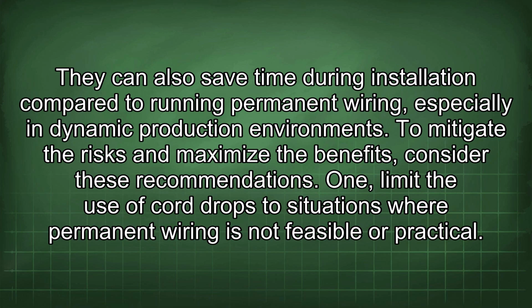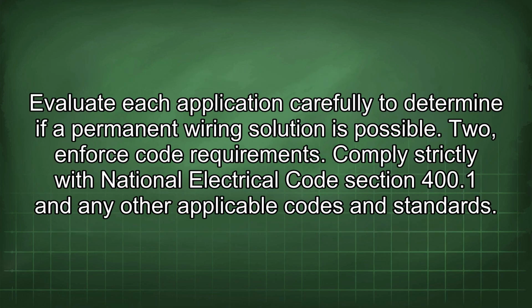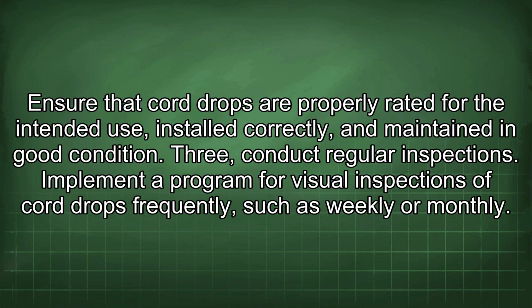1. Limit the use of cord drops to situations where permanent wiring is not feasible or practical. Evaluate each application carefully to determine if a permanent wiring solution is possible. 2. Enforce code requirements. Comply strictly with National Electrical Code Section 400.1 and any other applicable codes and standards. Ensure that cord drops are properly rated for the intended use, installed correctly, and maintained in good condition.